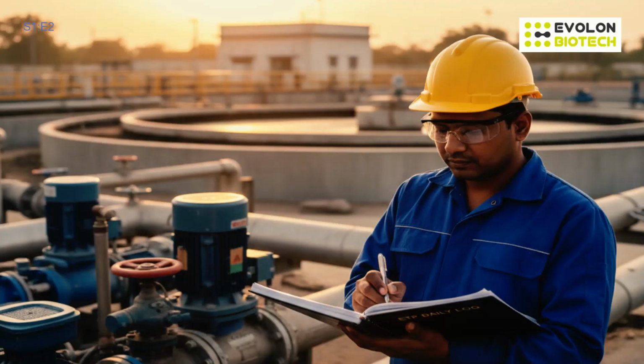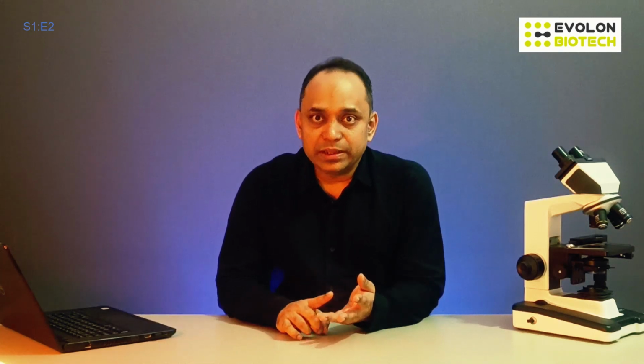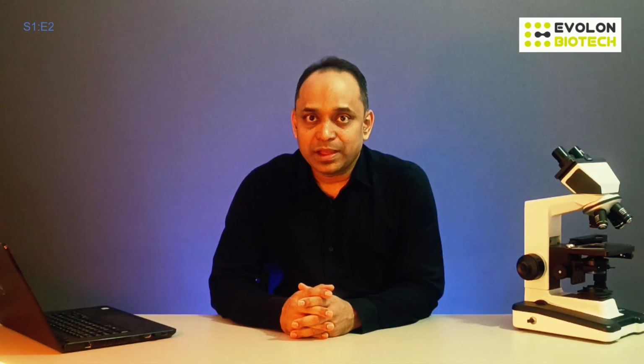And yes, maintain a logbook, a journal, where you will monitor everything that is happening in your plant. This logbook will teach you a lot. Log everything: the COD, the BOD, the MLSS, the color of effluent, the pH, and the changes in pH, the temperature if you can. On what day, what stream was let in your plant? What was the pH change that happened? How much alkali or acid was added? And so on. And let all these entries have dates.